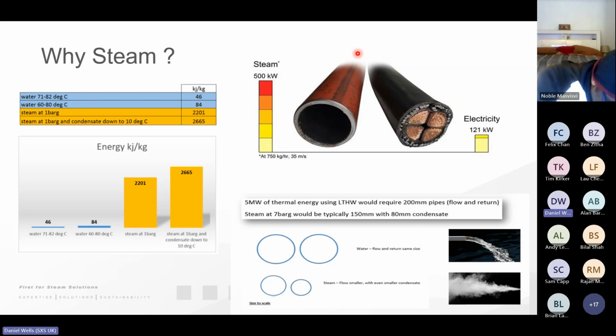So if we put all of those facts together, when we're comparing a traditional steam system to hot water that's produced by an air source heat pump, we need to remember, first of all, because there's far more energy in steam than hot water, it means that we're going to have to provide a sufficient number of air source heat pumps and at a sufficient capacity. We're also going to have to pump that hot water. So we're going to have to provide a number of circulating pumps that are also going to require an electricity supply.